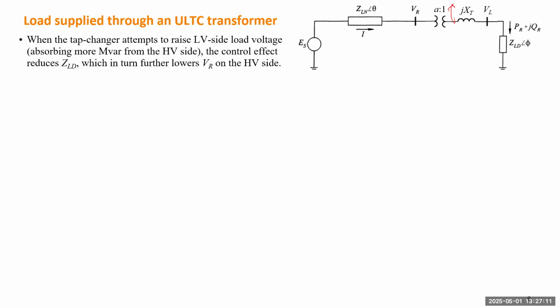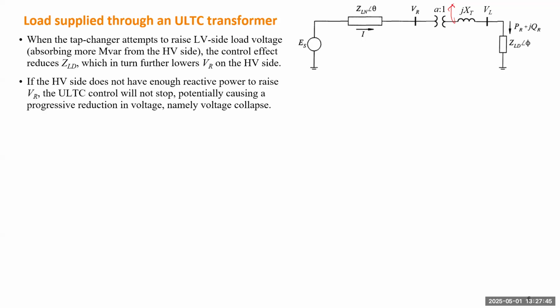So when the tap changer tries to raise the low voltage side, it basically needs to absorb more reactive power from the high voltage side. So the control effect actually reduces the load impedance, which is the same as what we just described from previous slides. So if the transformer together with the load operates at a highly loaded condition, it doesn't improve the voltage, it actually makes the voltage even worse. If the high voltage side doesn't have enough reactive power to support the voltage, this control cannot stop. It will just continue raising the tap and finally can cause voltage collapse.